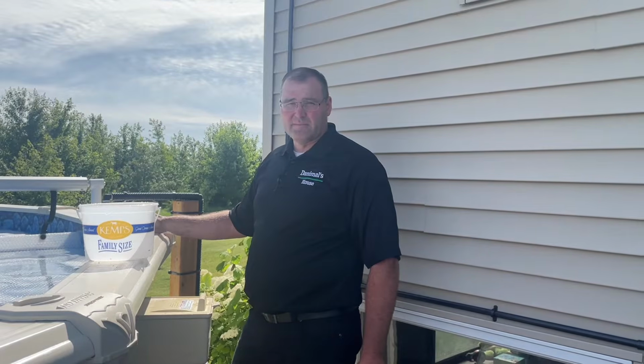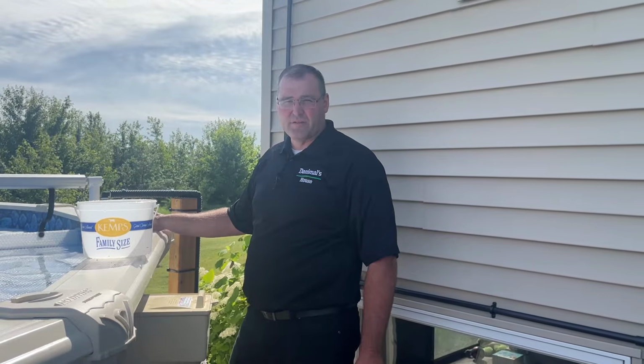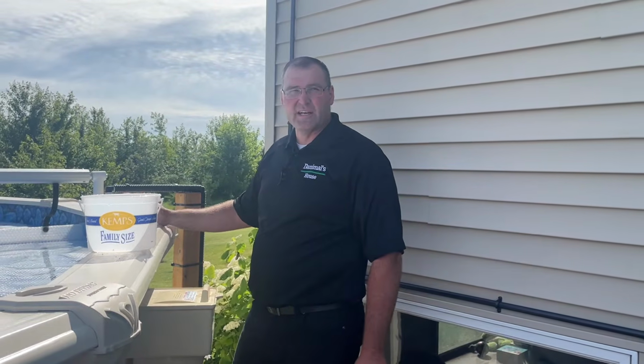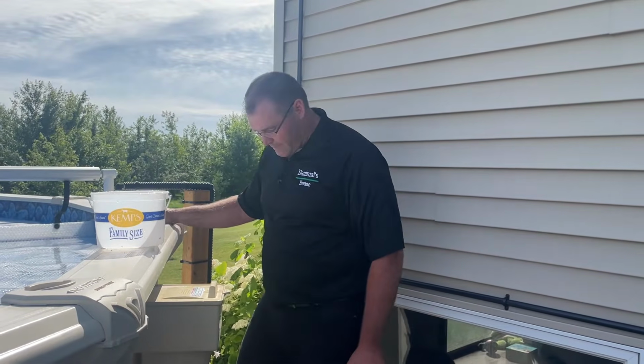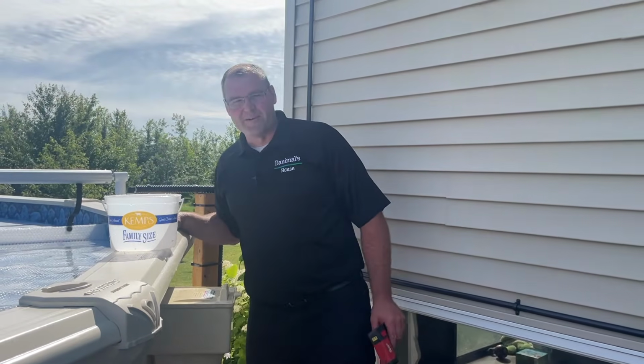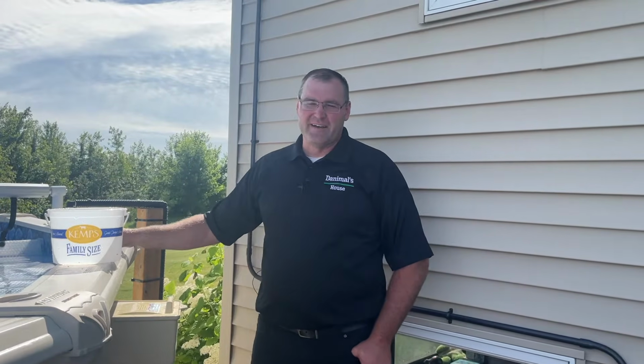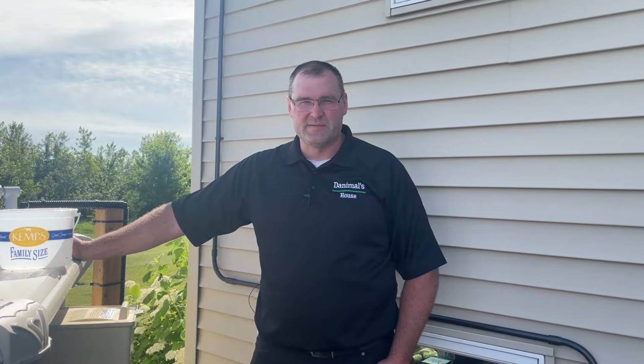That's big time. You're talking like 250, 300,000 BTUs of energy getting into that flow to make that happen. If you remember what I said with my old pool heaters, the first one I said was 17-degree temp rise at 1.5 gallons a minute. Think about how much more this is, it's like 10 times that. The other one I said was maybe 30 to 40 degrees temp rise at like 3 gallons a minute.